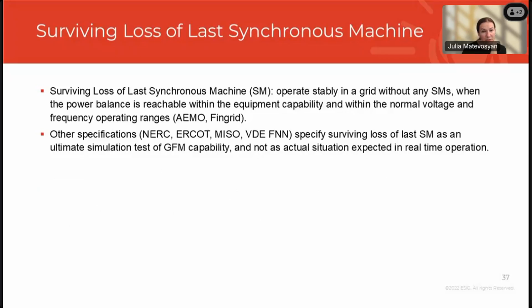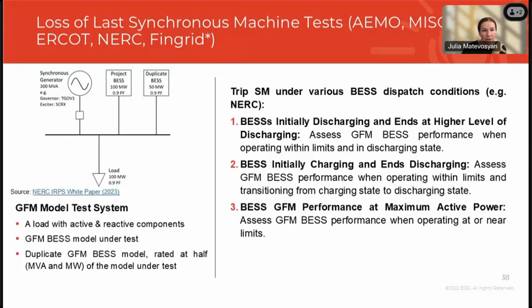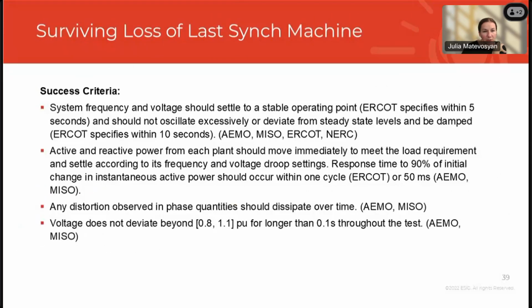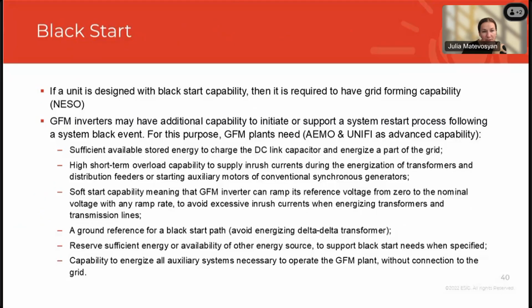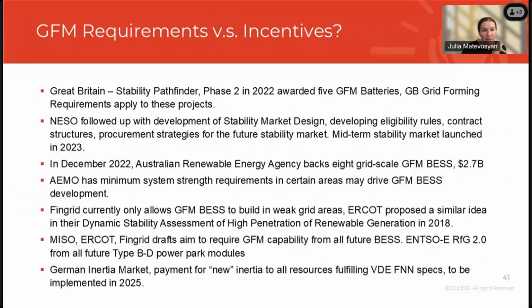and Fingrid, this is defined as a possibility, so something that can happen, that grid forming inverter-based resources may end up in an island without any synchronous machines, while other specifications look at that as an ultimate test for grid forming capability, and it's not something that can actually happen in reality. And the tests are just to see how the grid forming resource responds. I have a description of the test here on the slides, so again, you can look at it later. Black Start capability is something that is defined in AEMO and UNIFI as an advanced capability, and this list talks about what kind of additional capabilities are needed from a resource to be able to provide Black Start.